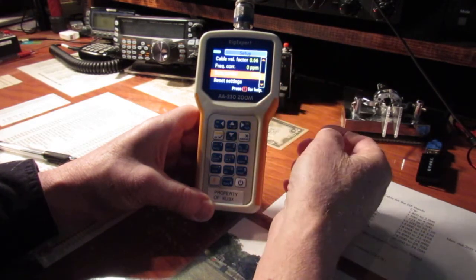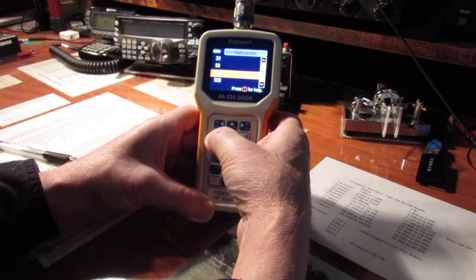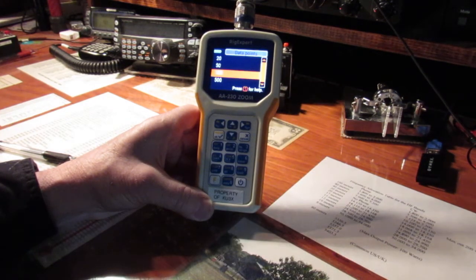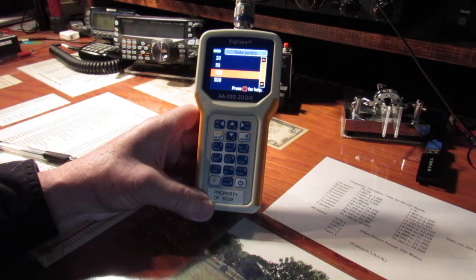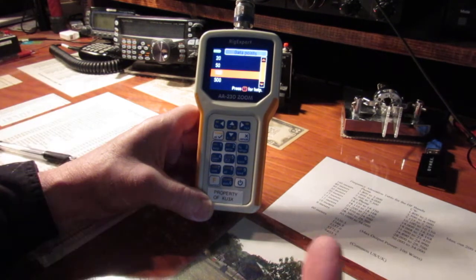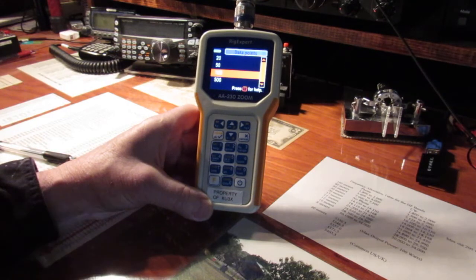Now here's the big feature. Sampling points. So right now I have it set on 100. That's a good range. As I said, the AA600 is only 80. So let's say you check a 100 kilohertz window. This takes a sample at every kilohertz, which is obvious, 100 sampling points. You check a 200 kilohertz window. This will take a sample at every 2 kilohertz.